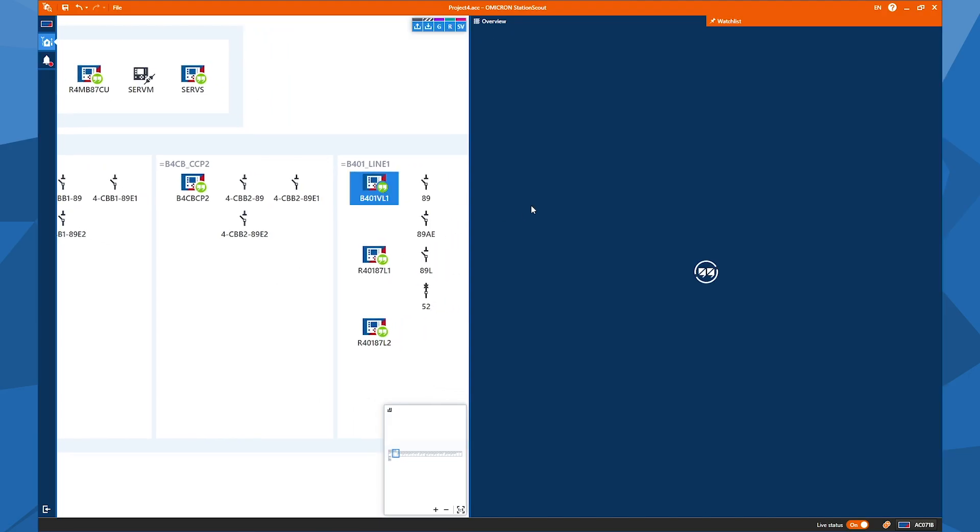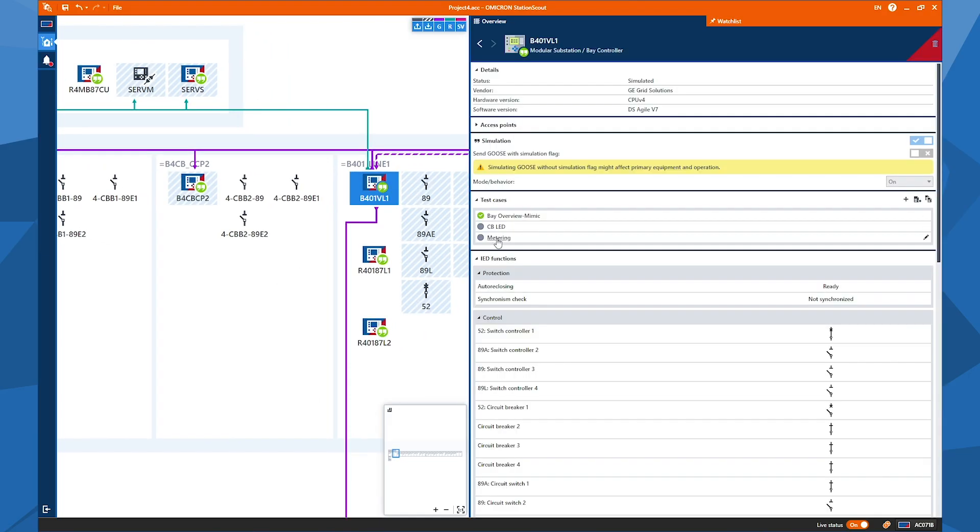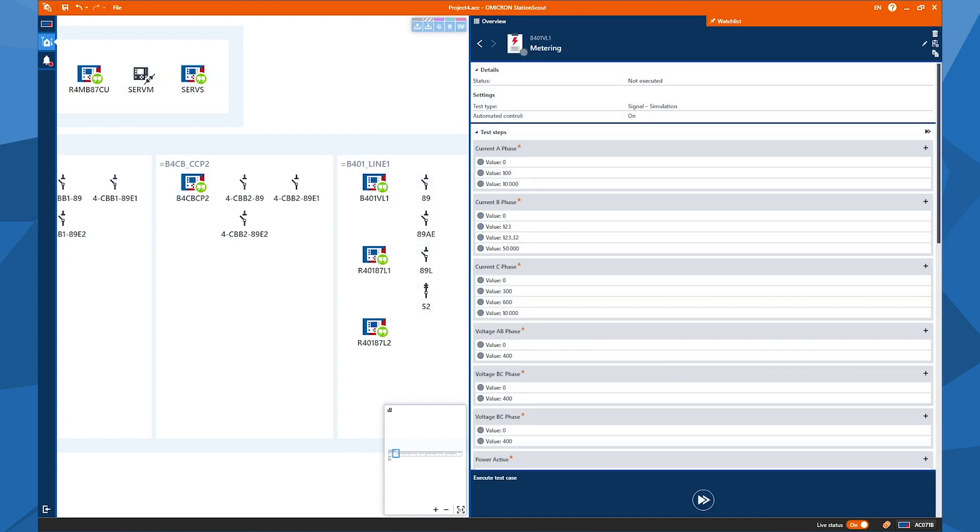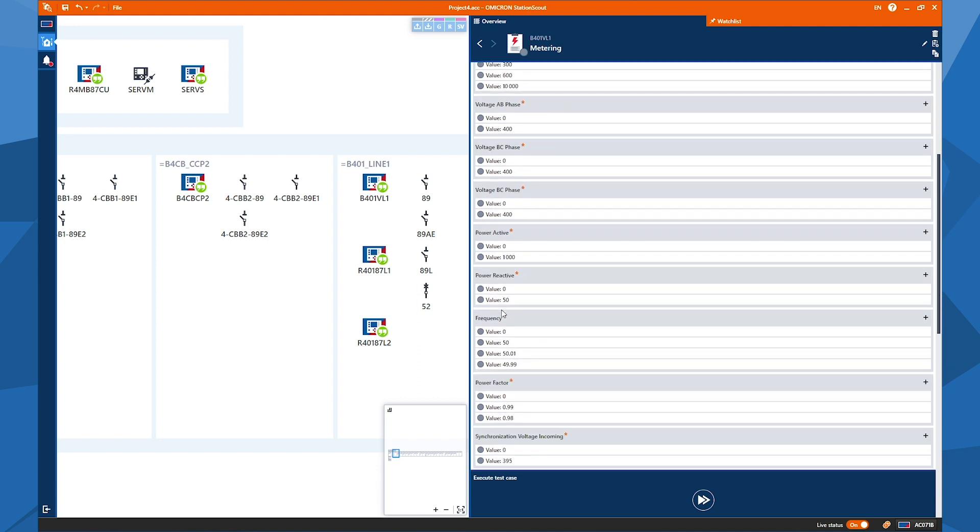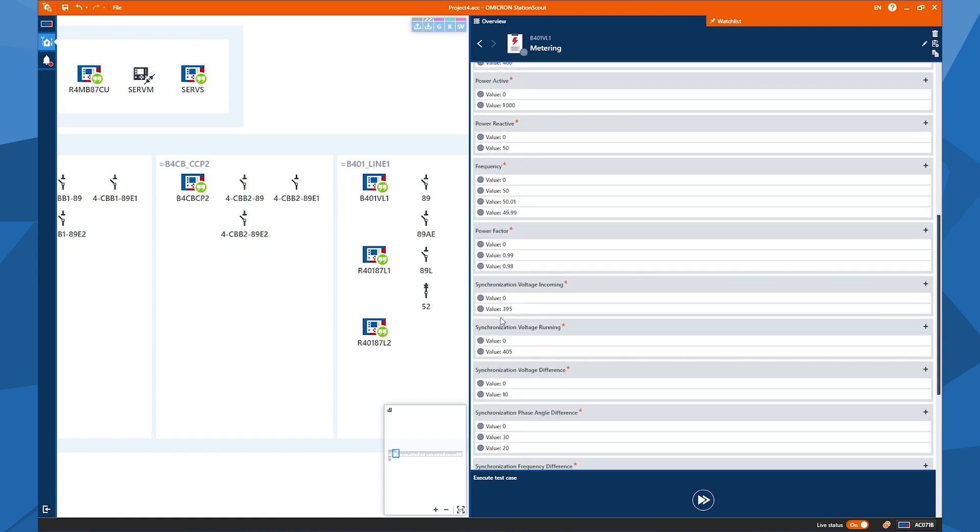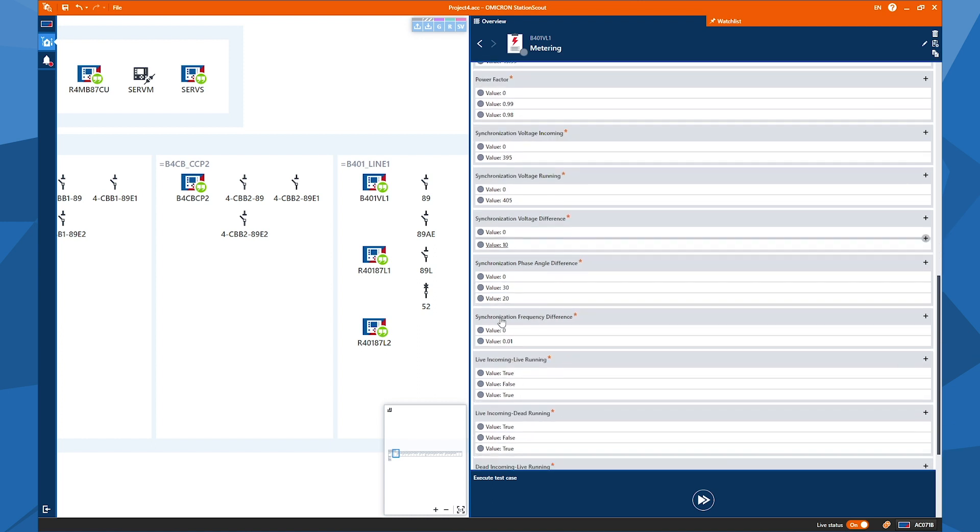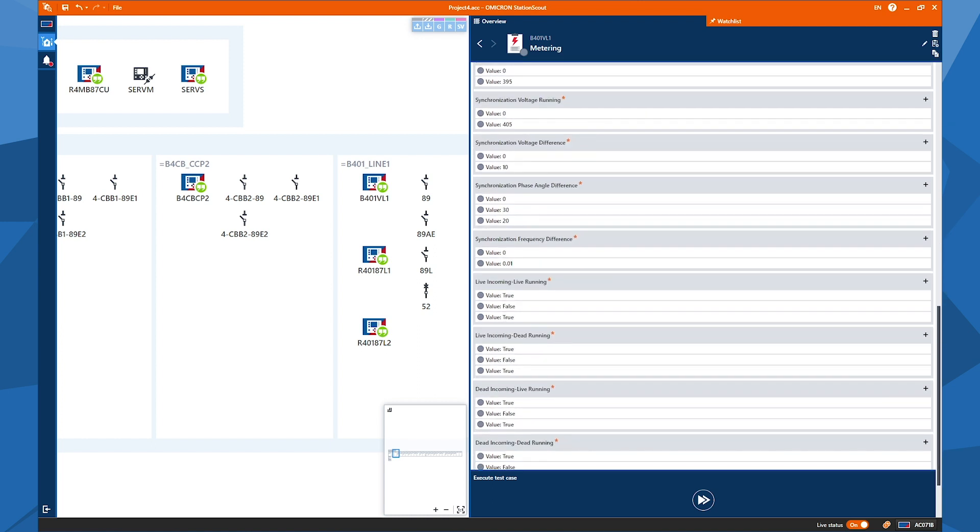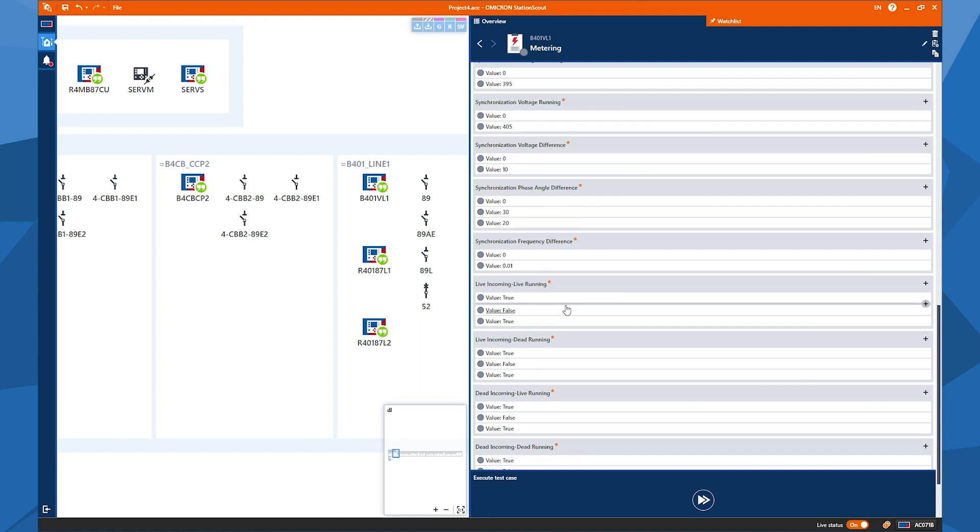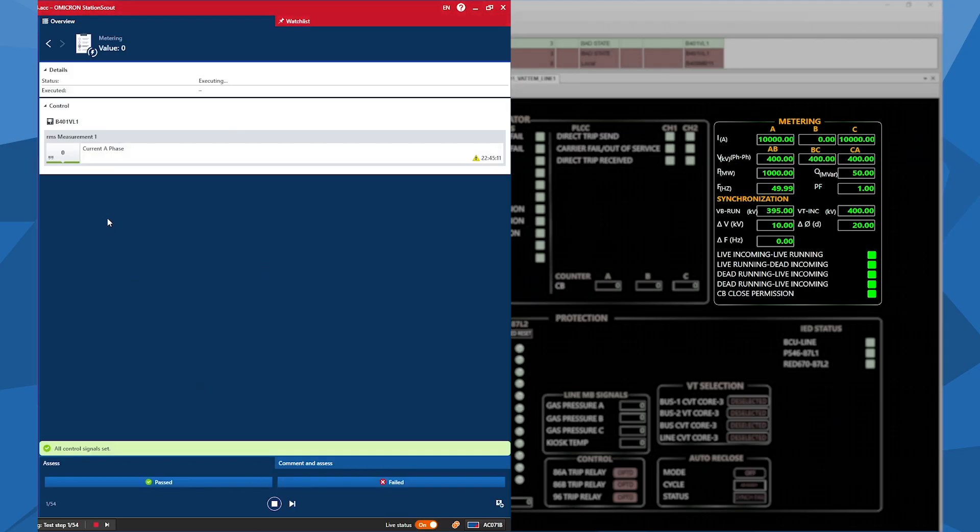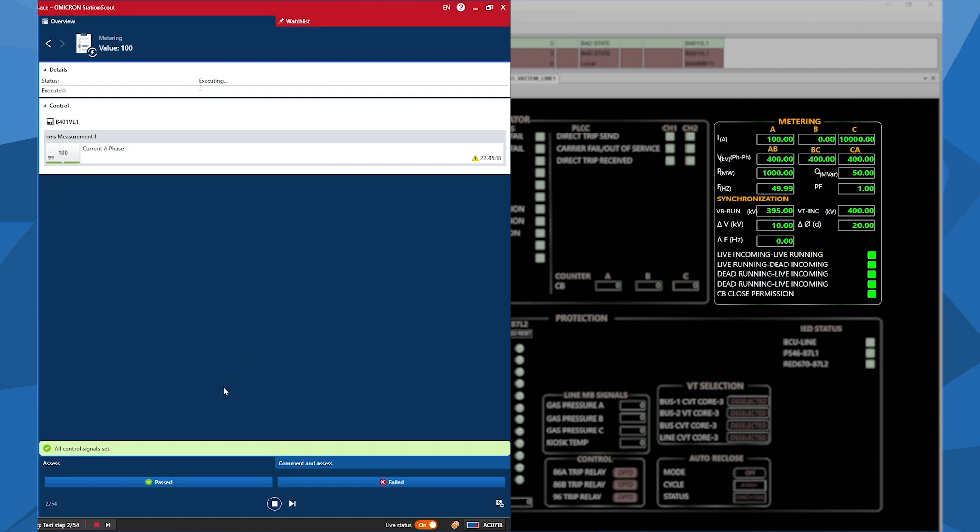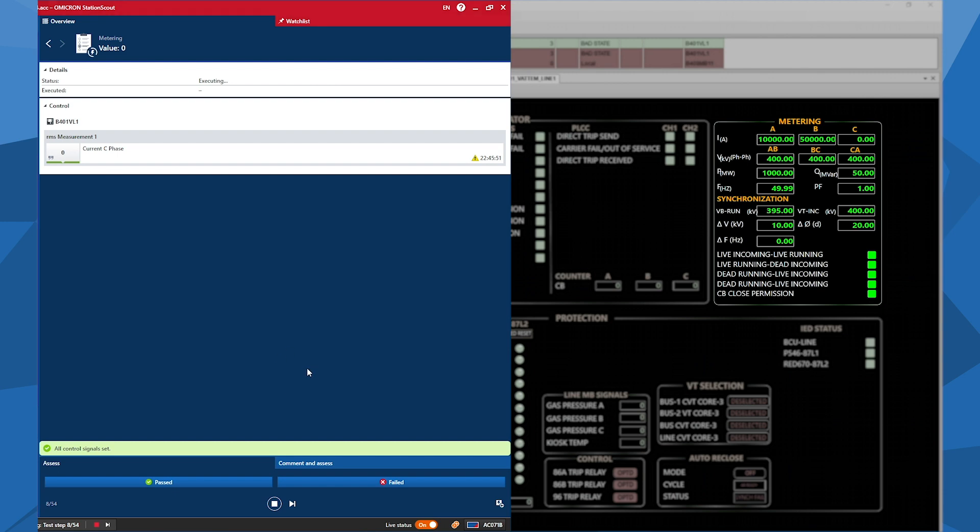And now I can switch to my next test, which is, let's say, let's test metering values. So metering values, you can see some strange values here. These are the already prepared or the actual status here. But I prepared the test case for current of A. We see following the phase-to-phase voltages, and then some active power, reactive power, frequency, just to show you all the different possibilities that's in this small diagram to be tested. So now we can start testing our metering values. So now the phase A current should be zero. Now I see that it's zero. Now I can say that it should be 100. Yes, that's true. With that, you can test all your values. I will not go further. It's the same, nothing different. But this is just showing you how to test the metering values.